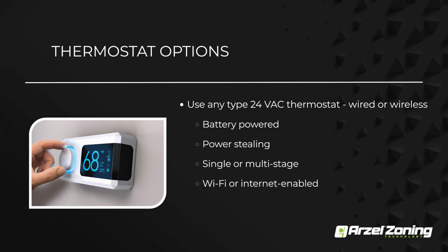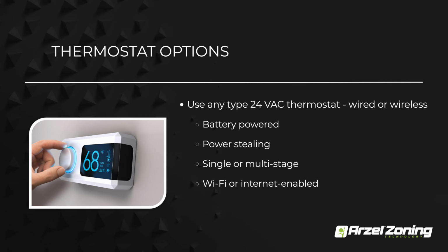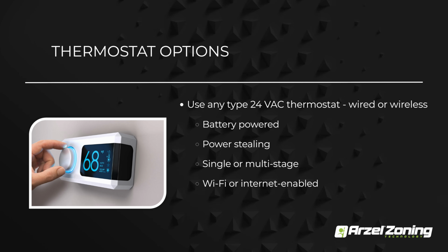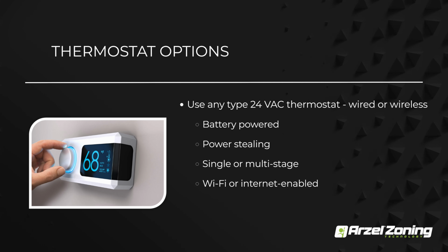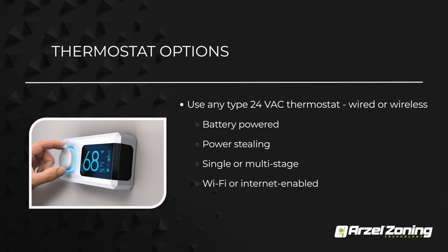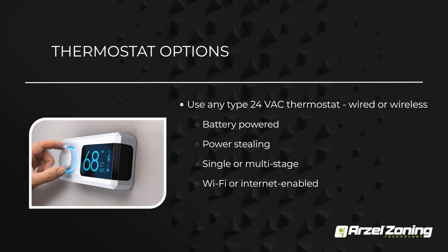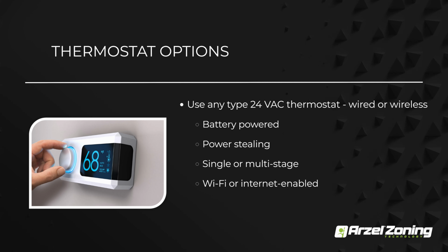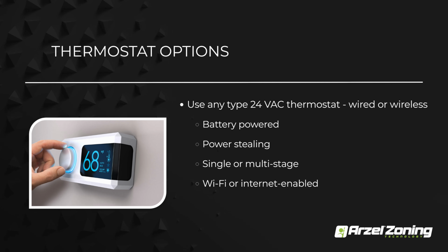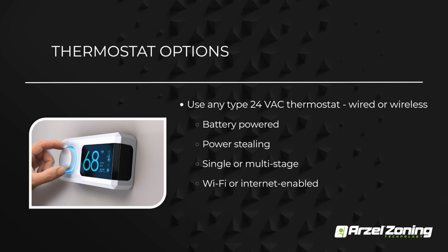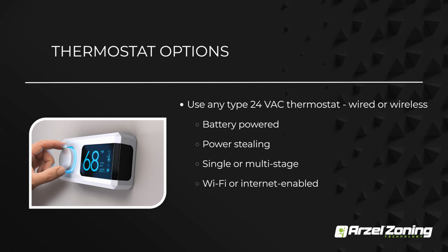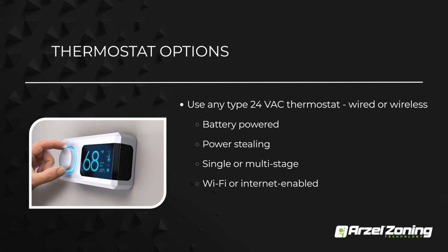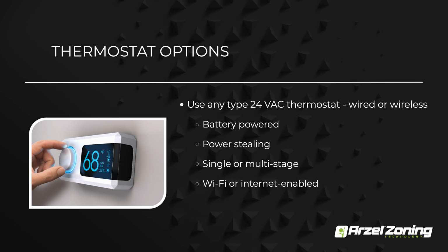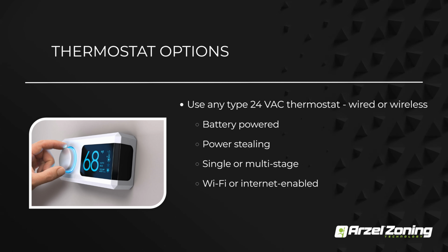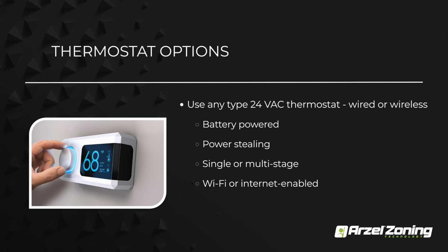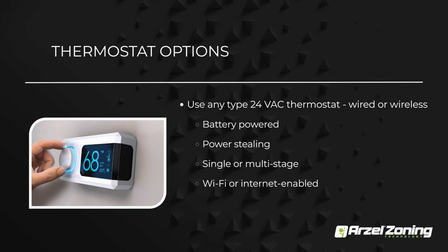If you guys are doing our AirBoss MPS panel, anything like that, you're going to want to match the application to the thermostat. So if you guys are doing a geothermal or a heat pump application, make sure you're using heat pump thermostats with those panels. If you guys are doing our Heat Pump Pro panel, you can use just single stage heat cool stats. Anything you guys are familiar with, if it be Wi-Fi, wireless, smart thermostats, if you got a customer that likes Nest or something like that, you can use that as well.